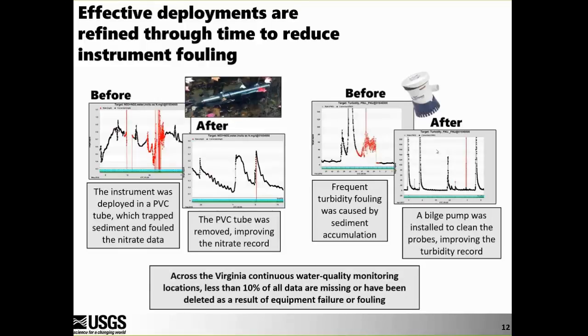Throughout our continuous water quality monitoring networks, we typically maintain greater than 90% of the data measured in the field, meaning we remove or lose less than 10% due to fouling or instrument failure. If you find you're having to delete months of data from an annual record, it's time to think about how that deployment could be modified and improved.